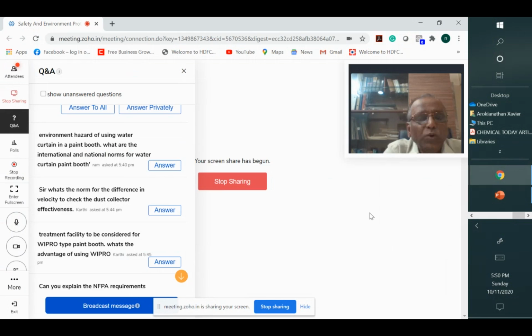Now I'll tell you, filtration technology itself is a technology by itself. When you are ordering a dust collector, the manufacturer should get the correct specification: what is the nature of the dust, what is the type of dust, what is the particle size of dust, what is the temperature of the dust, and is it hygroscopic? You have to analyze everything and then choose the appropriate filter media for that particular application.